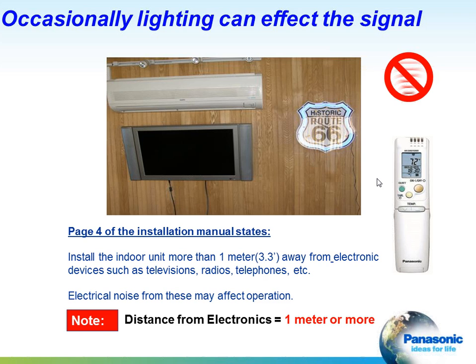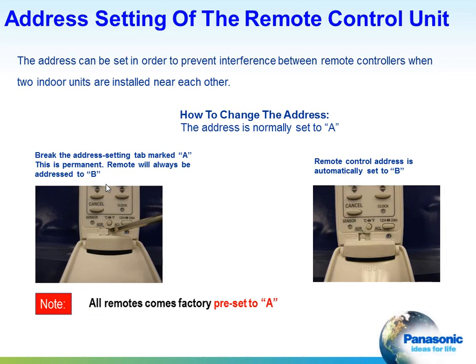Installation practices are important to this unit. Try to avoid close proximity to electronic devices and lighting. Electronic devices and lighting devices sometimes give off radio emissions that can interfere with communications between the remote control and the indoor unit. If you have 2 indoor units in the same space, let's say a very large room, you can still achieve zone control with those. You can set one control to control one unit and the other control to control the other unit. You can have different set points or different fan operation, whatever is best for the customer.